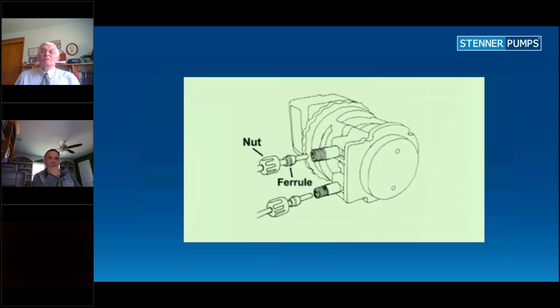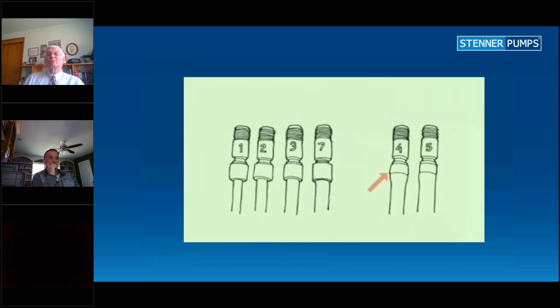The suction and discharge lines are installed to the pump tube fittings with a compression type seal consisting of the connecting nut and ferrule. The beveled end of the ferrule faces the tube fitting, and the suction and discharge line should bottom into the tube fitting. The connecting nut is secured into the fitting finger tight only and not tightened with pliers or wrapped with thread seal tape. Pliers or thread seal tape should not be used because the pump tube fitting is secured to the tube material by an internal seal consisting of a crimped brass collar, and on some of the tubes, the brass collar is under a rubber collar. Using pliers will break the internal seal and cause the tube to leak, and using thread seal tape will interfere with the seat between the connecting nut and ferrule.